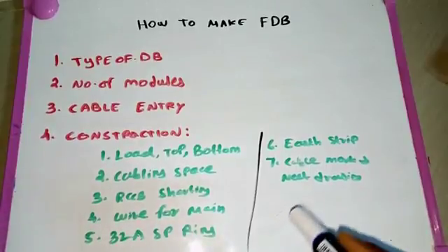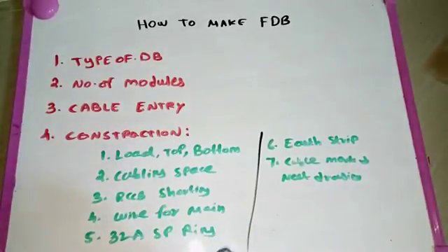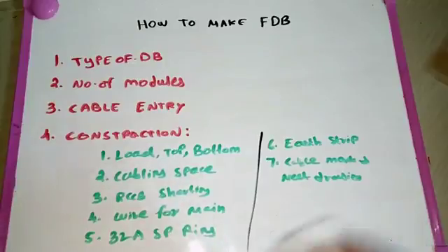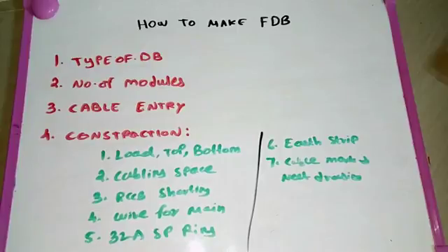The first thing is the type of DB — what kind of DB we need. There are weatherproof DBs, row type DBs, and some special split type DBs available. Row type DBs come in single row, two row, four row, five rows, etc. Weatherproof DBs use enclosures like 800x600x200. Split type DBs are already constructed with splits, so we simply install the breakers and connect the wire.